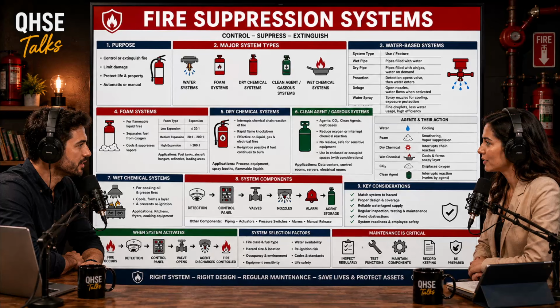And the jet engine hangar? Completely different hazard profile. It's a massive drafty structure with huge quantities of Class B flammable aviation fuel. A clean agent gas would be utterly useless here. The massive volume and drafty doors mean the gas would just blow away.